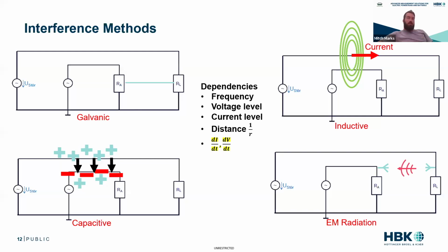We have inductive-based interference, where a current carrier, like my inverter cables with their high frequency, has high currents that create a magnetic field. This magnetic field can get picked up by my measurement cable and induce a voltage. Here we have dependencies of frequency, current, and distance between the two cables, effectively ending up with the function di/dt, the change in current over the change in time.